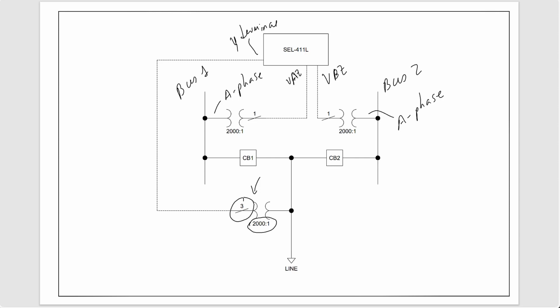Now, as I mentioned, this is a 230 kV transmission line, which means that if we have 2000 to 1 PT ratios for all of our PTs, the secondary voltages are going to be 115 volts line to line on the Y terminal and 66.4 volts line to neutral on the Z terminals. And of course, 115 line to line equates to 66.4 volts line to neutral. So it's the same ratio for all of the three PTs, but again, we have a three-phase connection for the line side and single-phase connections for the bus sides.